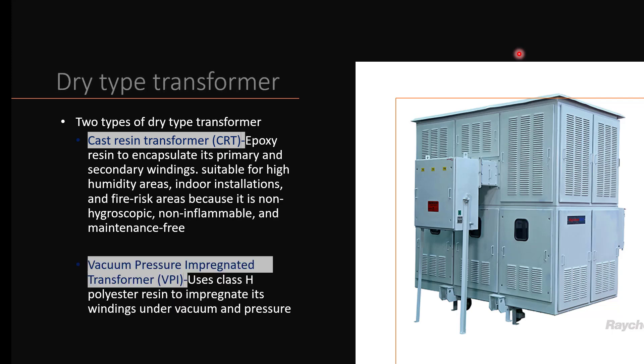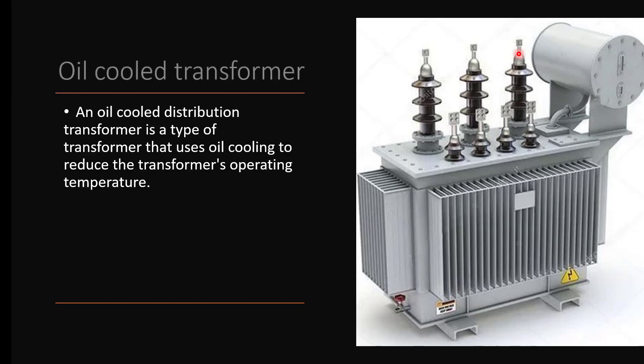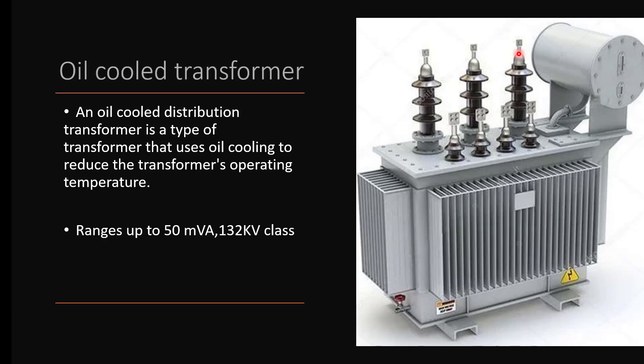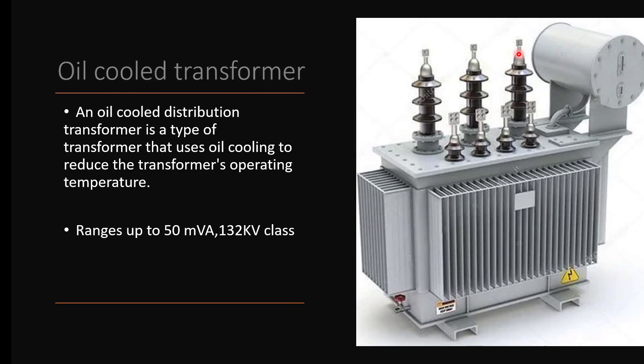Another dry type transformer is the vacuum pressure impregnated transformer (VPI). In this transformer, using pressure under vacuum, a polyester resin is forced to penetrate into the windings. The next commonly used transformer is the oil-cooled transformer. In this type, oil is used as the insulating and cooling medium to reduce the transformer operating temperature — up to 50 MVA, 132 kV class. It is the most commonly used outdoor transformer. If we don't provide a cooling medium, the heat produced in the transformer windings will cause it to burn. To avoid that, oil and air are used as cooling mediums.